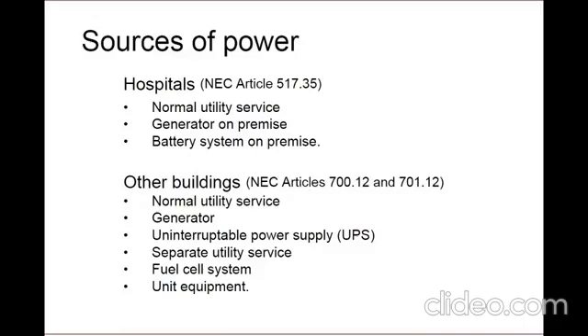Emergency systems in other building types have a few more options. Again, the normal supply may be the local utility. The alternate supply may be a generator, a battery system, a UPS, a fuel cell system, or unit equipment, such as battery packs and lights. Where approved by the local AHJ, a second utility service that is completely separate from the normal supply may be permitted.